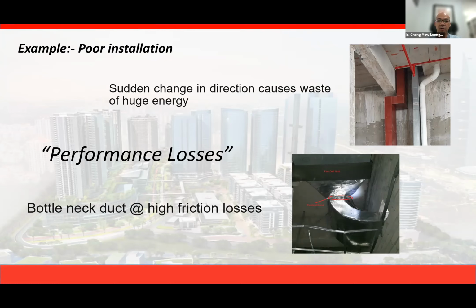So try not to have all this. This is obviously from the coordination purpose - you can see the ducting trying to avoid the beam, diverting to the opening as shown in the drawing. And the bottom picture shows the FCU - I call this a bottleneck duct because of the way they installed it, they squeeze the neck of the FCU, resulting in high velocity losses.